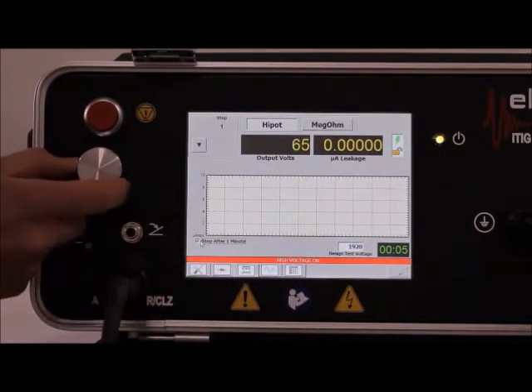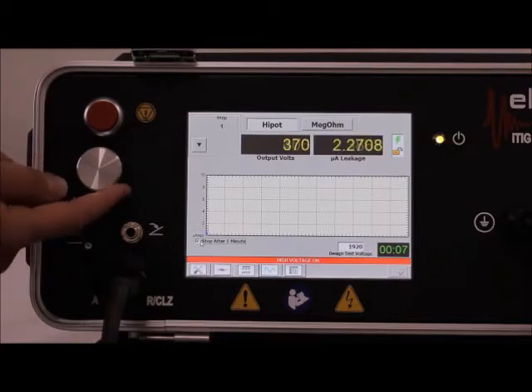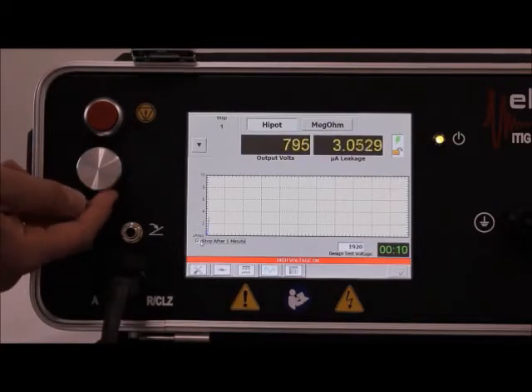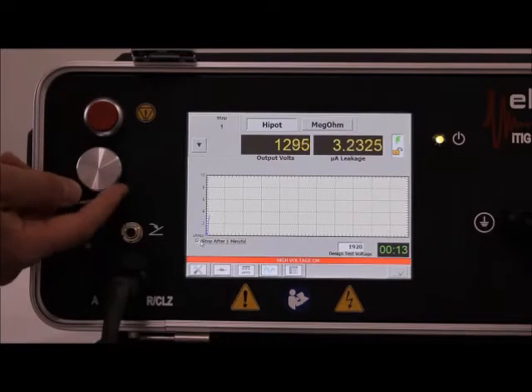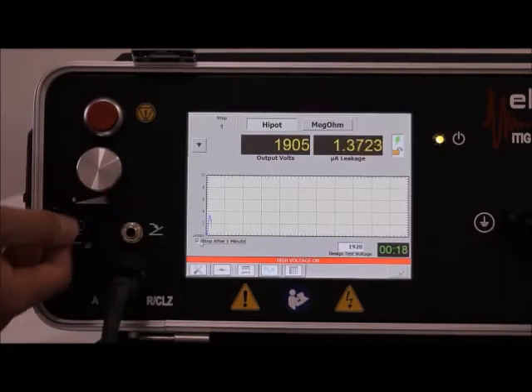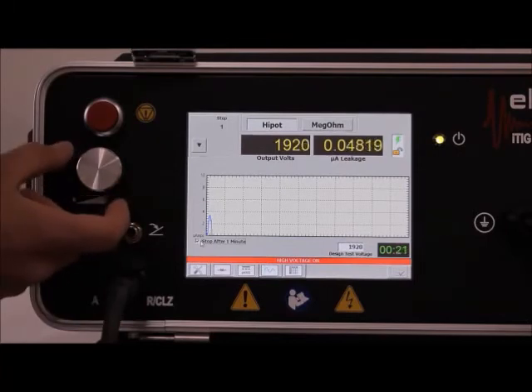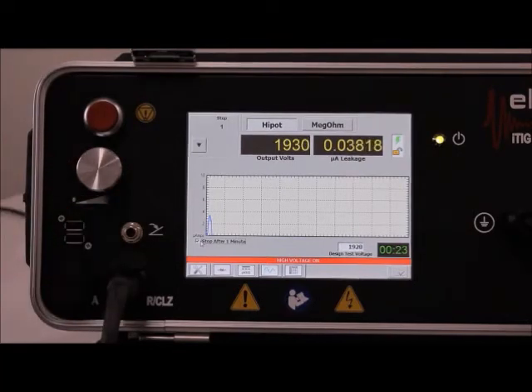The assigned test voltage is 1920, as defined on the setup screen. Turn the silver dial up to approximately 1920. Let's see how close I can get. Right about there. Now if we let it sit for a minute, the leakage current will hopefully drop off. It's at this point 0.03 microamps. That's nice and low and still falling.